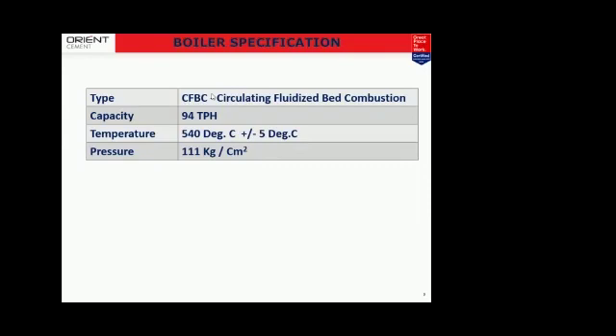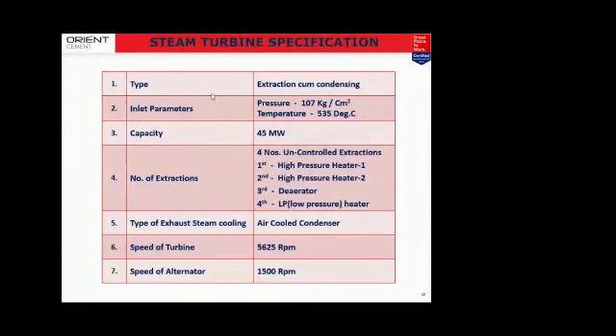The temperature is around 540 degrees centigrade, and it is a high pressure boiler, generating 111 kg per centimeter square. The turbine is an extraction cum condensing turbine, and as you can see on the screen, the pressure is 107 at the inlet of the turbine and the temperature is 535 at the inlet. It has 4 uncontrolled extractions. And we are using ACC, that is air cooled condensers, to cool the exhaust steam, not water cooled condensers.